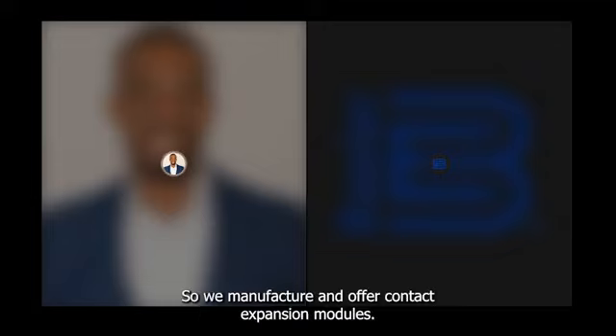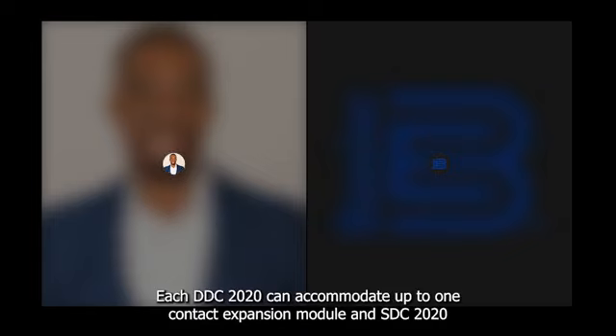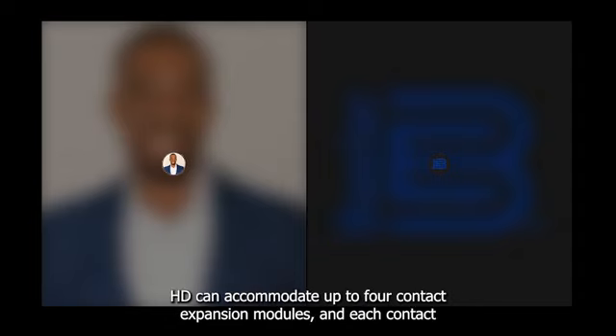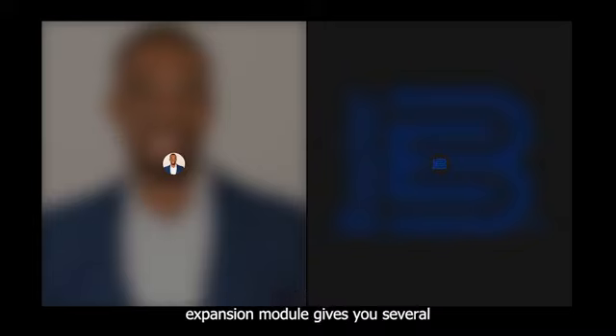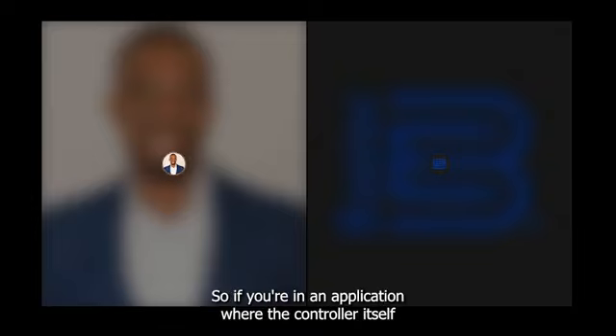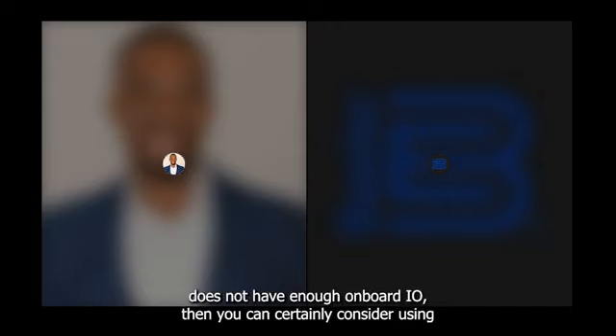So we manufacture and offer contact expansion modules. Each DDC 2020 can accommodate up to one contact expansion module, and each DDC 2020 HD can accommodate up to 4 contact expansion modules. And each contact expansion module gives you several additional digital inputs and outputs. So if you're in an application where the controller itself does not have enough onboard I/O, then you can certainly consider using expansion modules to increase the amount of I/O to give you what you need.